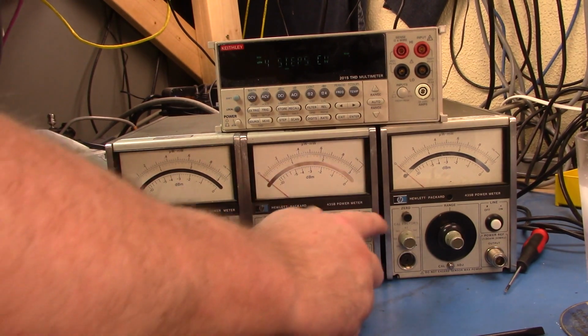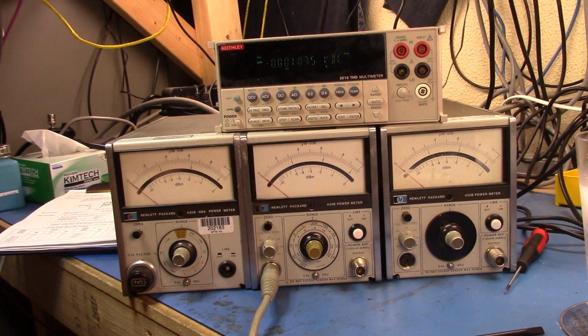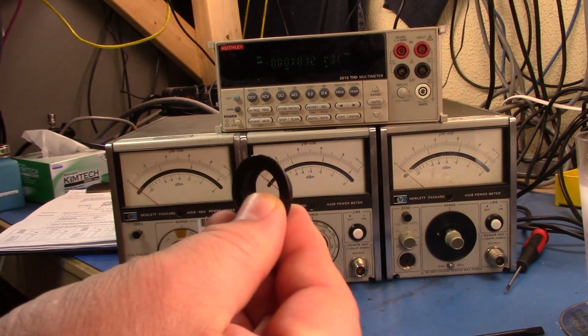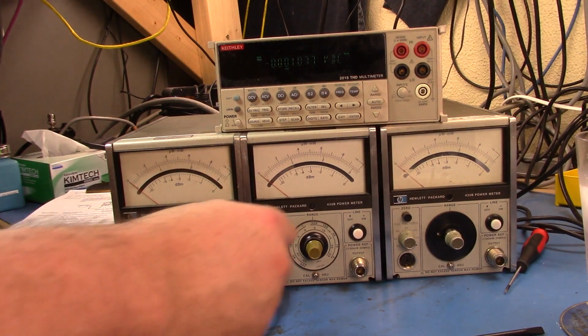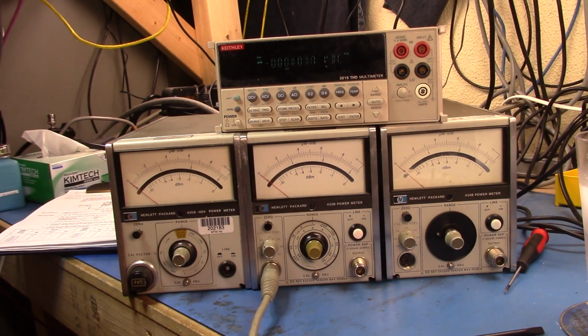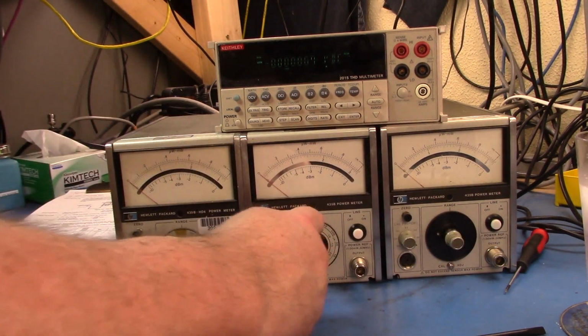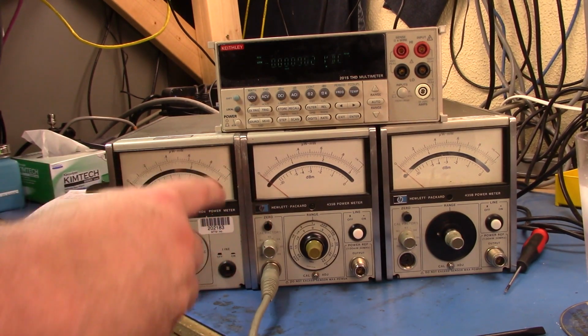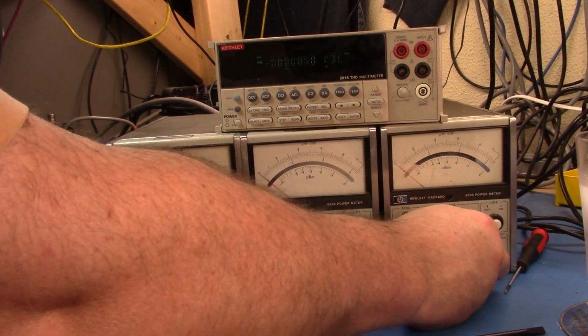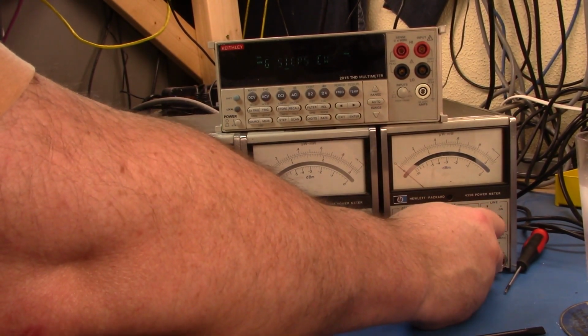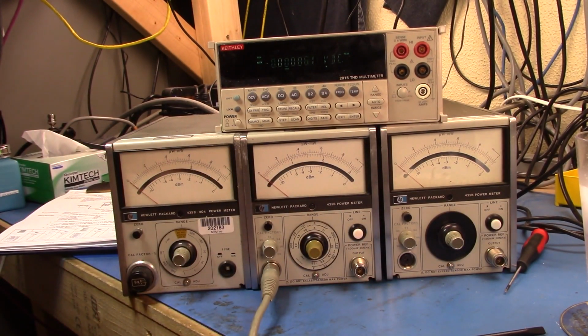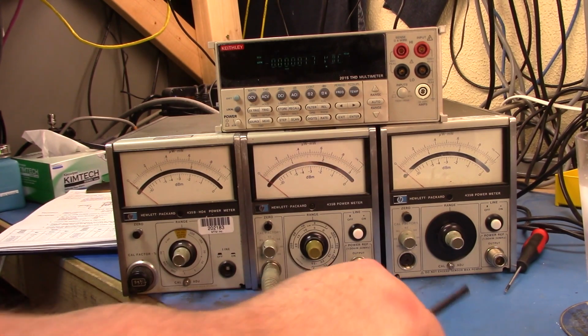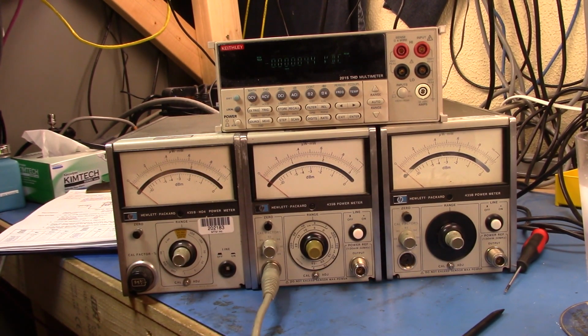What I need to do though is print more of the range rings. Basically, you take off this little cap, and you can see the cap here. We'll wait until this finishes and then we'll go to our next range. And then these rings will mount on here, and there's a bunch of different ones. They're also stored there, and they're designed to work with the various 848X power sensors. So you can have the right display in terms of the power you're reading based on the sensor that you're actually using. I need to print some more of those and laminate them or something so that I can put them on this machine here.